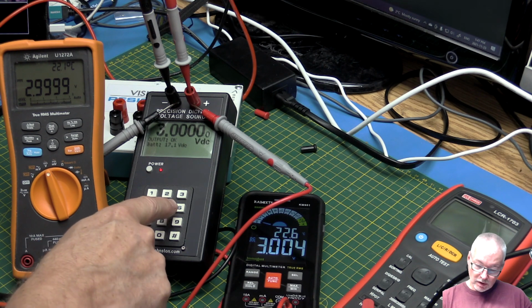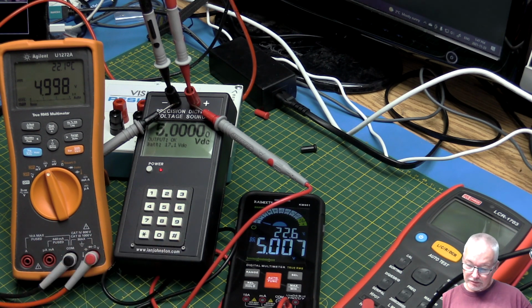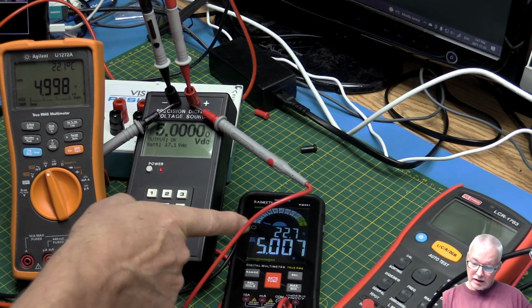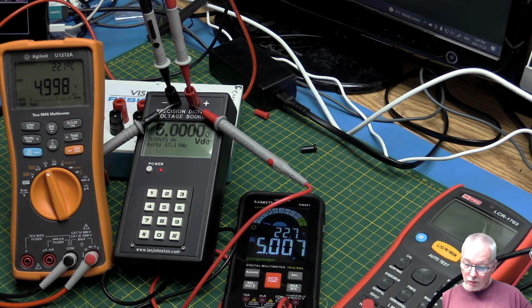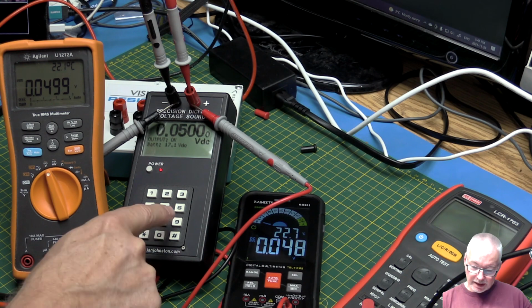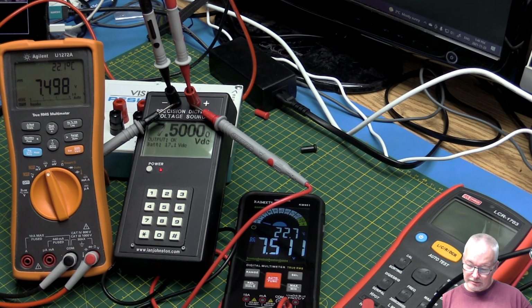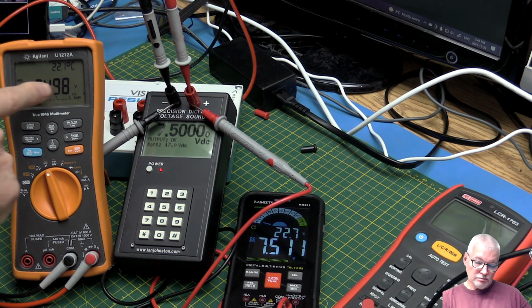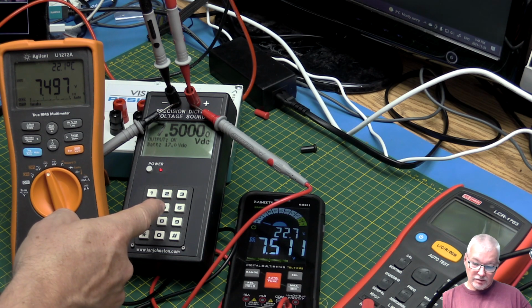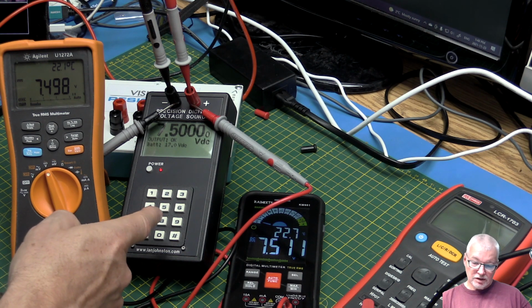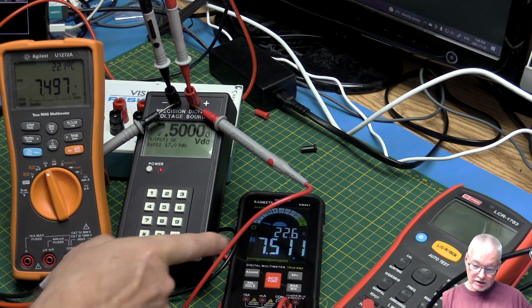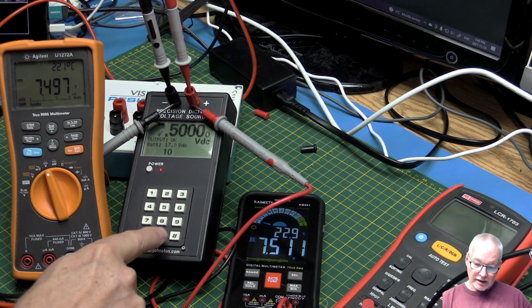Let's go to 5 volts. Again, it's staying within specifications. It's got that slight, basically a 0.1% offset there. Let's go to 7.5 volts. Again, this one is pretty much exactly spot on, just marginally out, but within its specification. This hasn't been on a huge length of time, so it could be just still settling down on its voltage references. Now let's go up to 10.